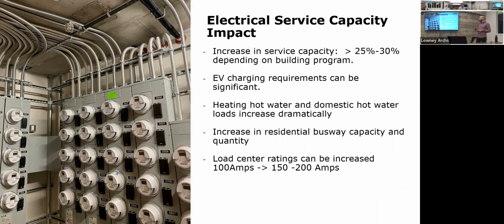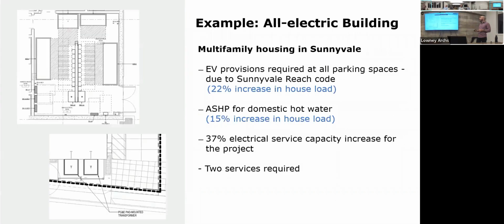And yeah, your load center ratings can be increased from 100 amps to 150 to 200 amps. As an example, I picked the multifamily housing project in Sunnyvale. For that project, because of the reach code in the city of Sunnyvale, all parking spaces had to be 100% EV ready, which is above the code requirement that you just saw. Again, it's a lot more stringent.